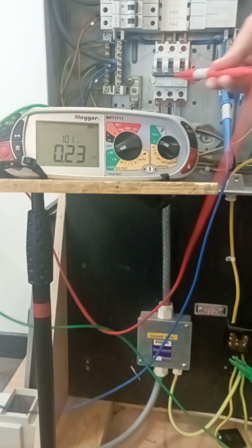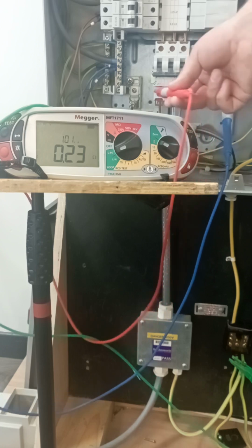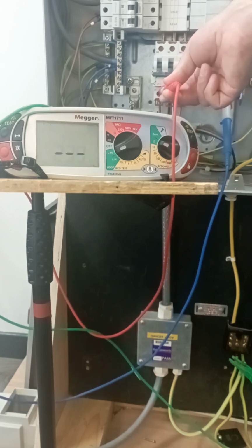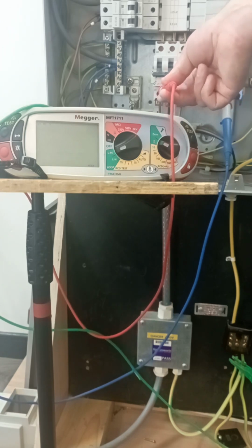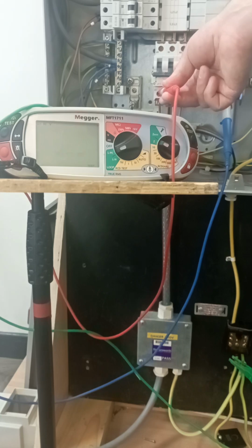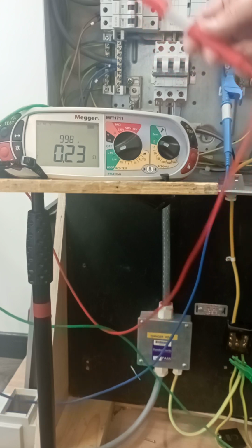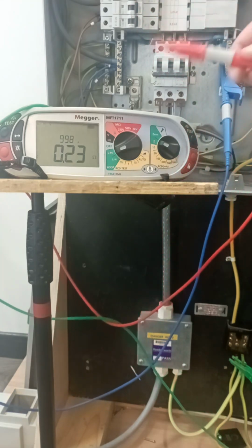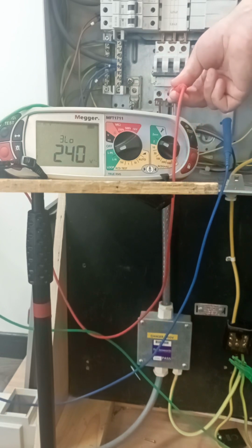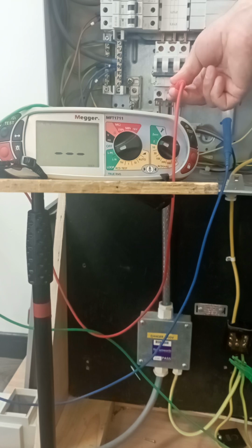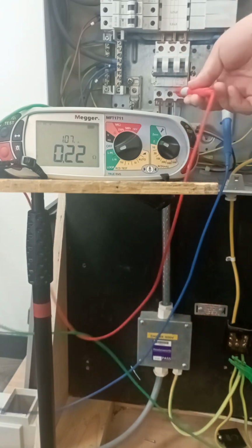Now again, with high current testing, we would repeat this process. Again, we're looking to see what impact those 18 amp dumps of current down the earth path have on our earthing conductor and its connections. So we're just stressing all the connections between that crocodile clip all the way back through to either the service head or the centre point of the transformer. So that's 0.23 of an ohm. 0.22, 0.22 of an ohm, and then line 3.